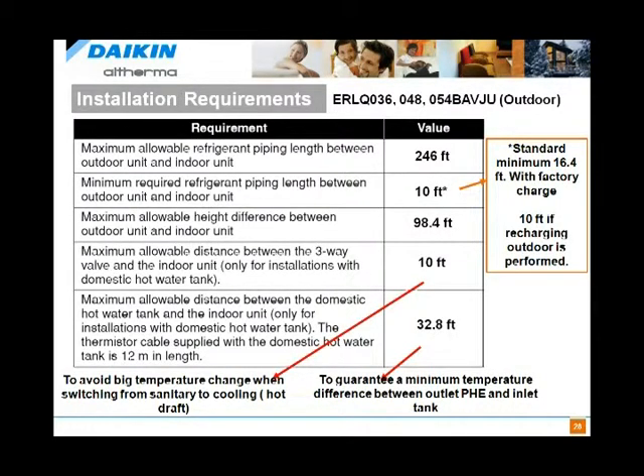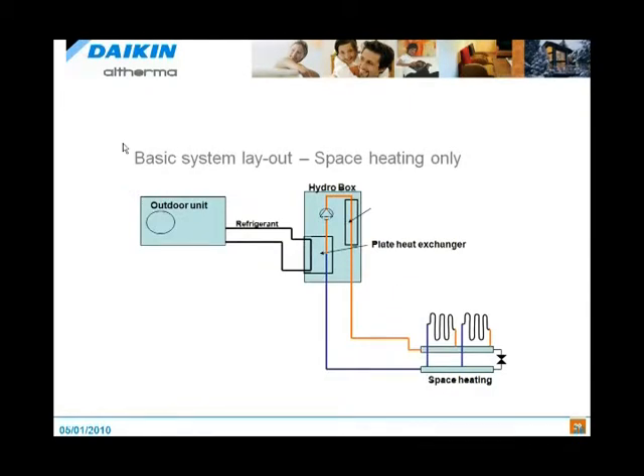However, the monoblock, in particular if you're using an indirect water heater, we want to have no more than 32 feet away from the house. So that's a limitation. On the other hand, the monoblock has the refrigerant all pre-charged and ready to go. So those are two trade-offs to keep in mind. So the basic system layout is you have an outdoor unit, you have the hydrobox, and you go out and do your space heating on a heating mode. Very straightforward.